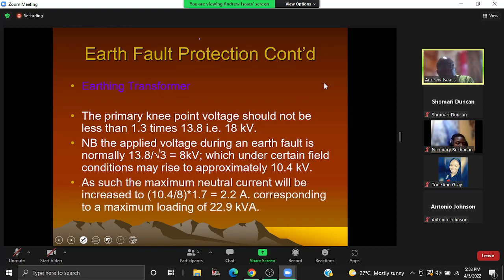So in terms of the neutral current, remember now that we had that at 1.7. So based on the change in terms of the voltage, based on that 1.3 factor, it means that the current will also have to increase by that factor. All right? So we get the 2.2. Yes, and we have the voltage. And that gives us the 22.9K.